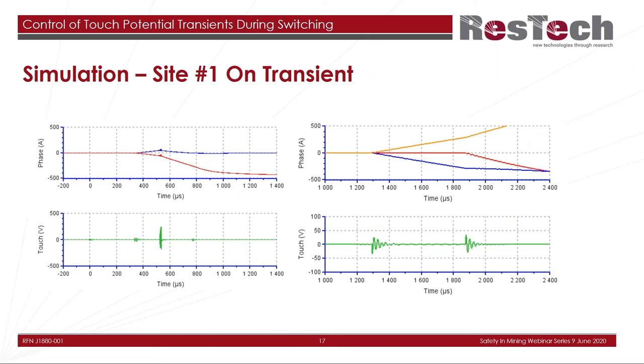So simulating these things, and this is just showing some simulations which actually have a much more complex model trying to show some of this more complex behavior. The on transient is actually not too bad trying to simulate. And in fact, basically the contact is coming in and it's that time delay between contacts which is the main contributing factor. Yes, you do have to get the phase between the contact coming in and what the supply is. But apart from that, it's actually not too bad trying to do it. What becomes difficult is trying to get the complex oscillations and patterns in the waveform, because you basically have a very complex machine with lots of complexity in there, and you have to actually simulate all those to get exactly the same waveform. But nevertheless, we do get similar sort of patterns appearing.